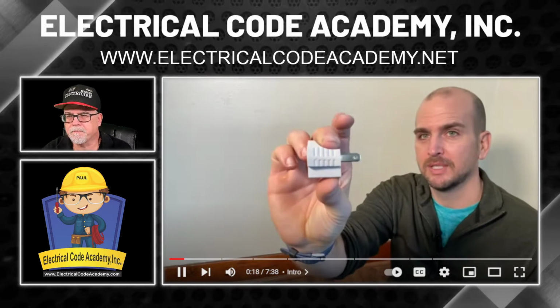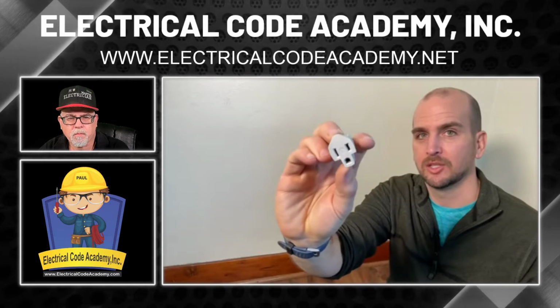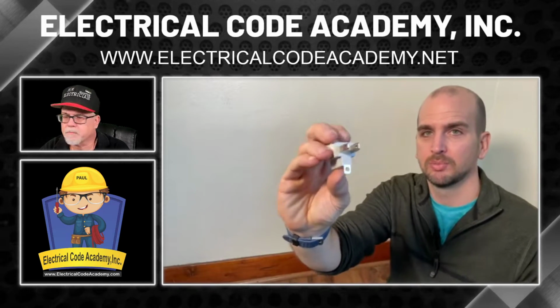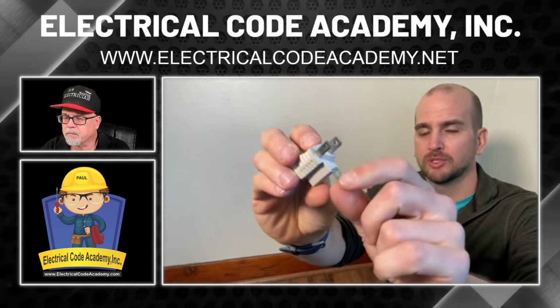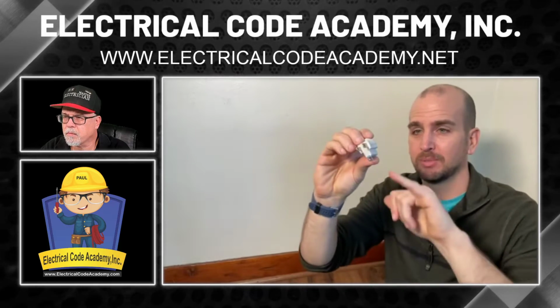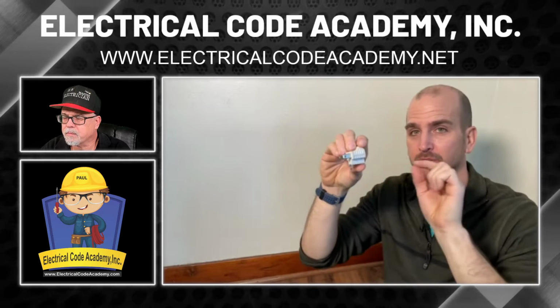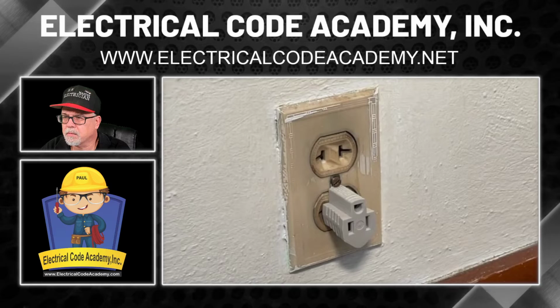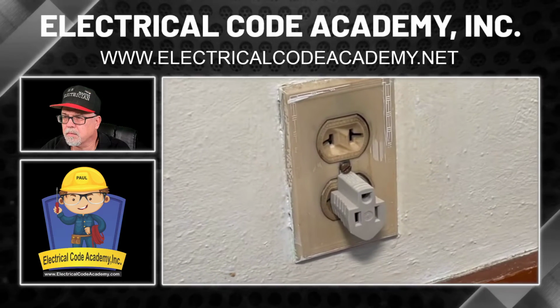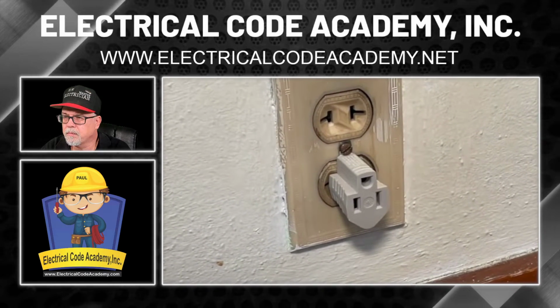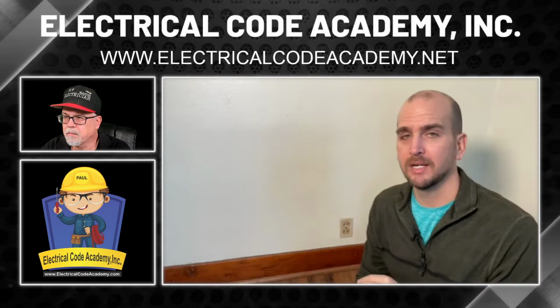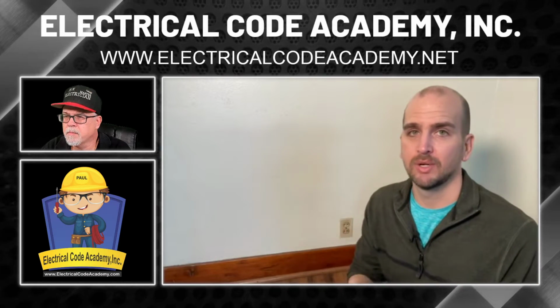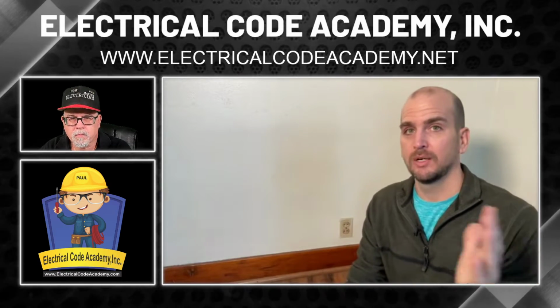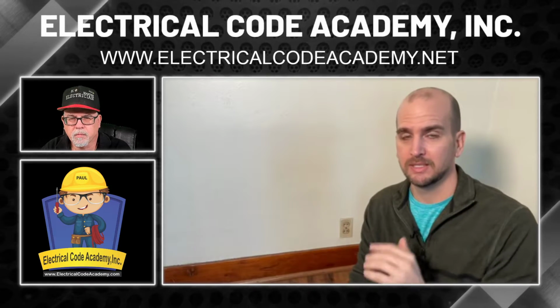To solve that, you might be using one of these adapters that takes a 3-prong and gives you that 2-prong. And it has an additional small strap here that actually some people screw in. So the screw for the faceplate right in the center here, they'd screw that in. Now that's not creating a ground because there is no equipment ground coming to this box. So it's just an unsafe way to do it. So let's get you upgraded to a 3-prong and do that safely.